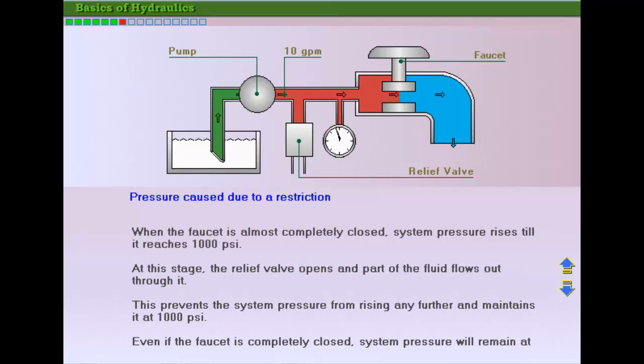The faucet is closed still further, and the system pressure rises. It reaches 1000 psi. The relief valve opens and part of the fluid flows out through it. This prevents the system pressure from rising any further, and the system pressure is maintained at 1000 psi.